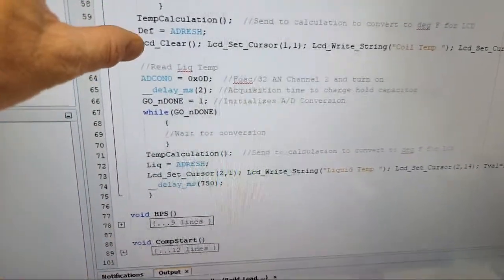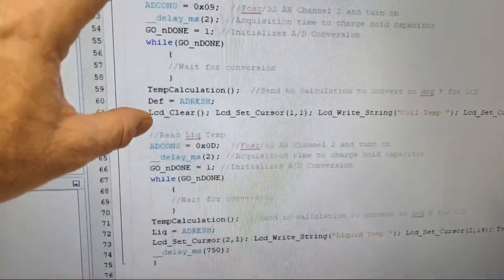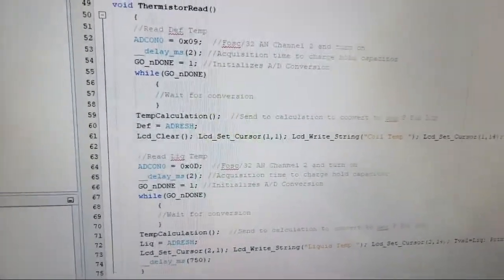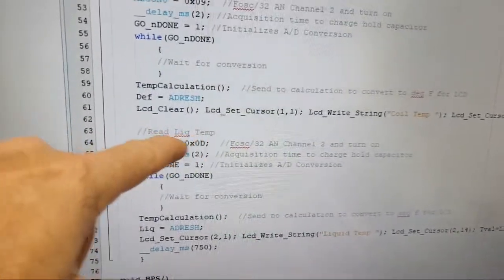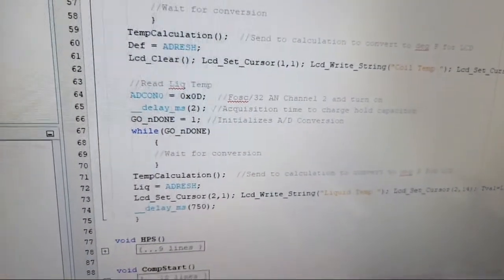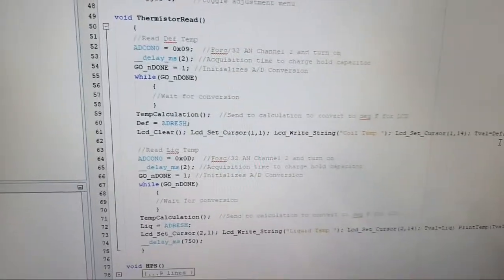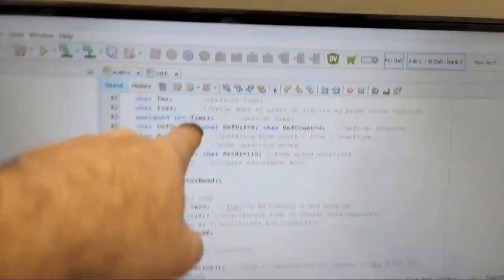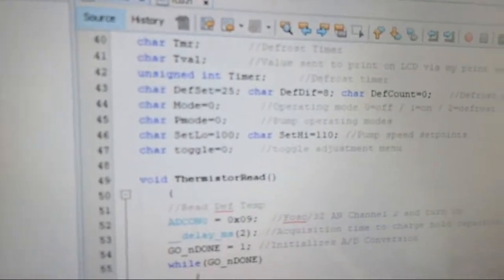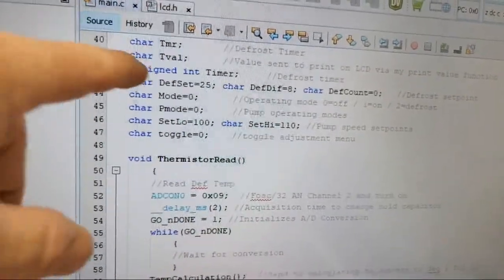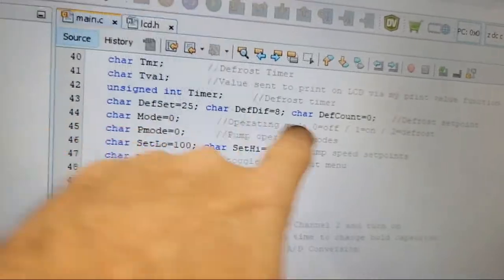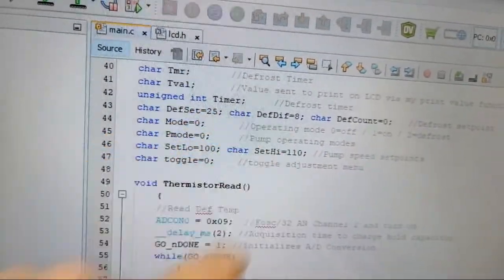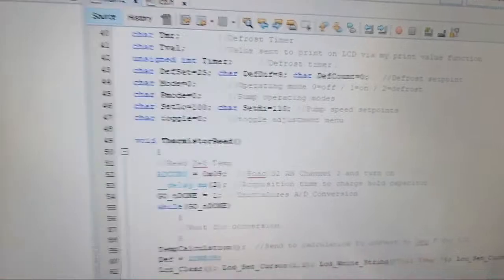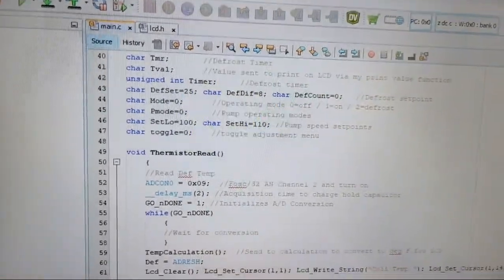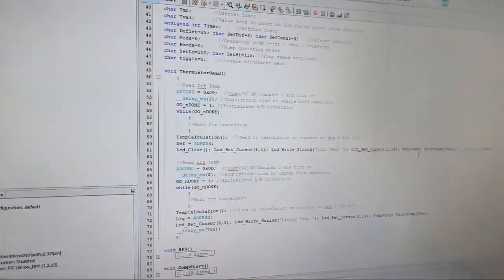So I'm just reading a defrost temperature, which is just a probe shoved in the coil out there. And then the liquid line one, which is the one that's controlling the pump speed. So in my code, I just look for it to go below like 25 degrees. I can adjust it with buttons once it's running, but when I first program it and turn it on, it just loads these values. So 25 degrees with an 8 differential. So when it hits 25 degrees, it's going into defrost. And I have a timer with a fail-safe timer, and then terminate on temperature.